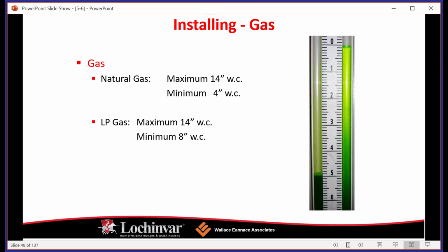So what you're going to need to do when you're installing the equipment is install your manometer on the gas valve of the boiler, and read how much gas is coming in from your service to your boiler. The maximum that we want to see is 14 inches of water column. The minimum is 4. For liquid propane, it's 14 max, minimum 8. Now, it's good to remember that doing the bare minimum is not what we want to see.